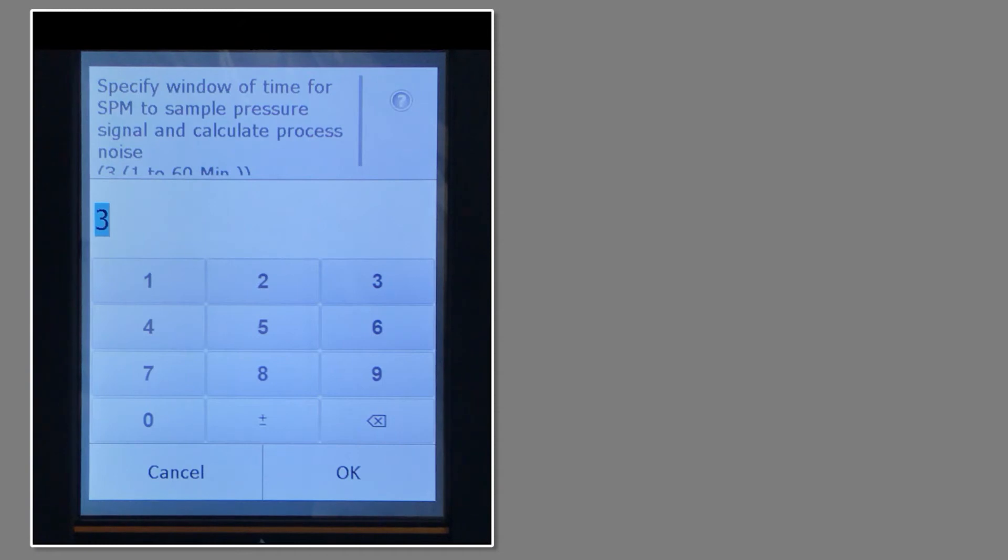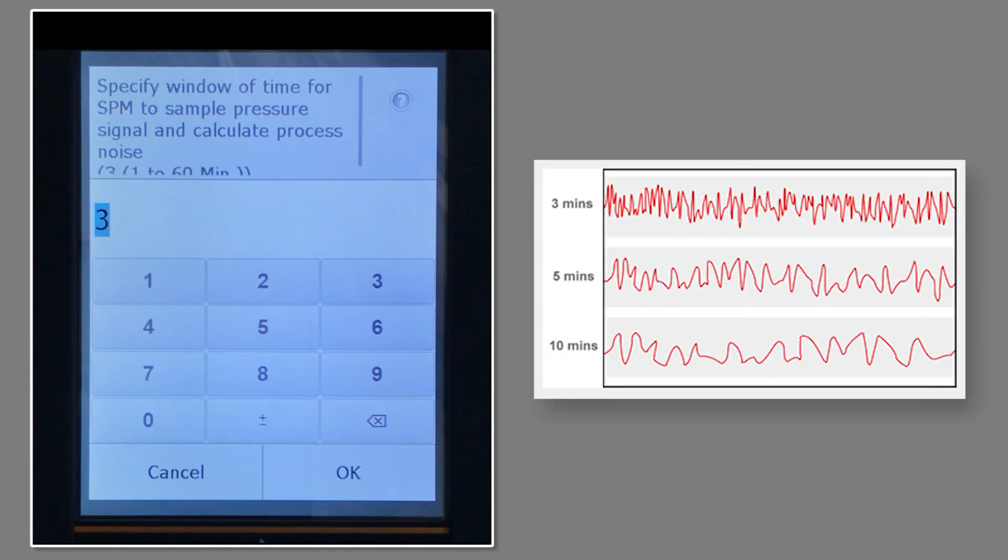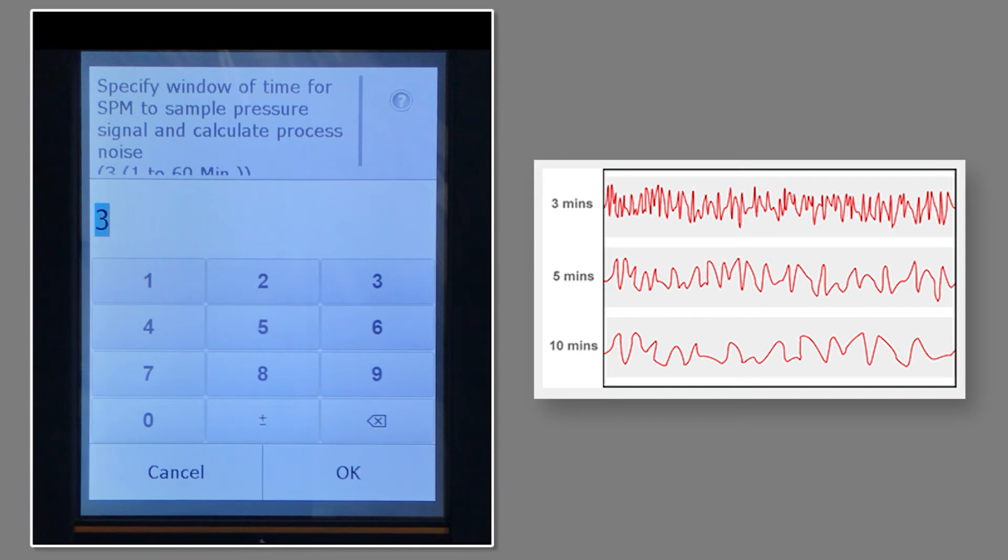Next is selecting the learn monitor period, which is the time needed for the diagnostic to learn what normal looks like in the process. The default is three minutes, but for more or less stable applications, more or less time may be needed. I'll be selecting three minutes.